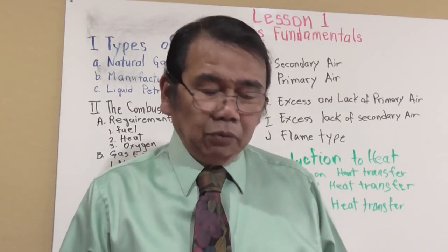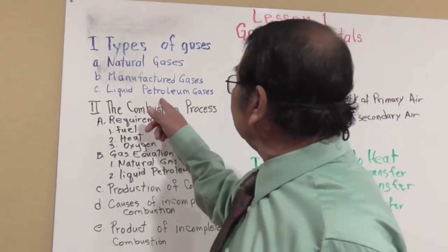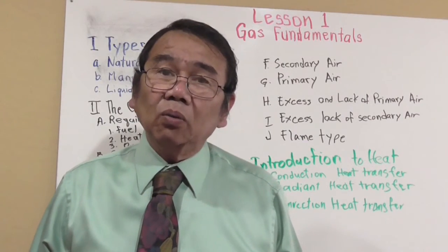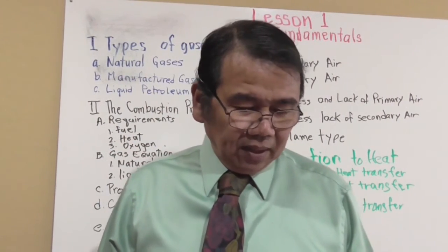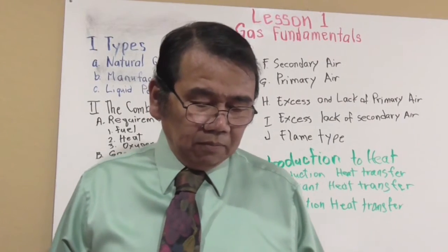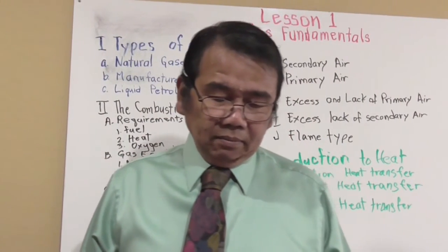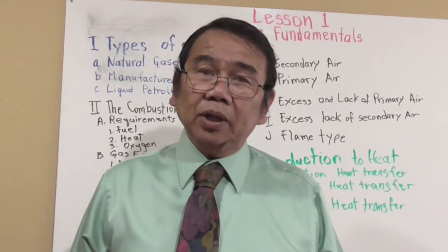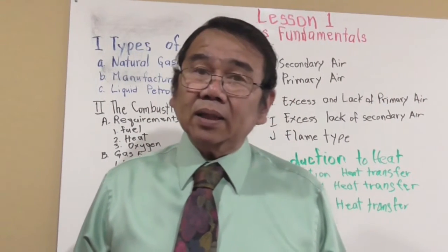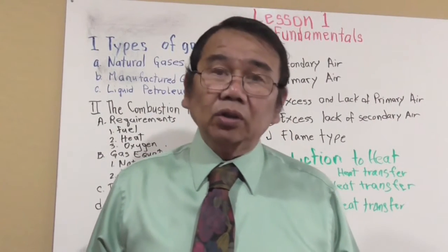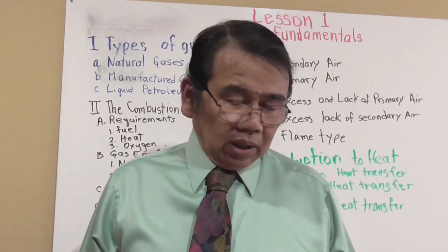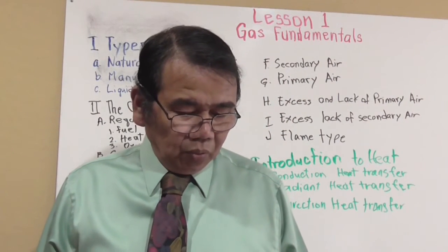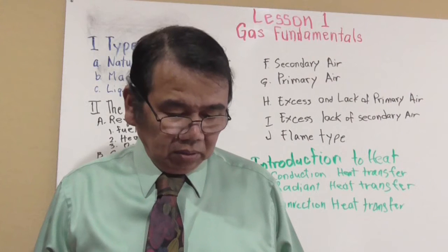Liquid petroleum gases, what we call LPG, are a combination of propane, butane, and pentane. Colorless and odorless. Odor is added. Heavier than air, will puddle in low spots.